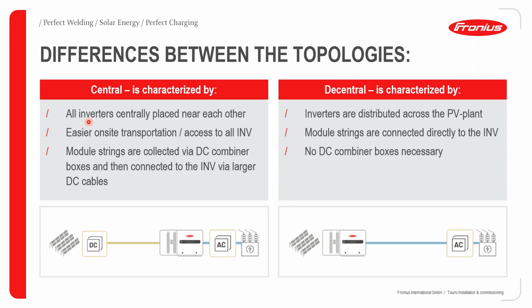The decentral design has the following characteristics: the inverters are distributed across the PV plant. The modules are directly connected into the inverter, and in this case, when you're doing a decentral design, this is also something to note, that you're not going to require additional DC combiner boxes, as all the strings will be connected into the inverter directly.